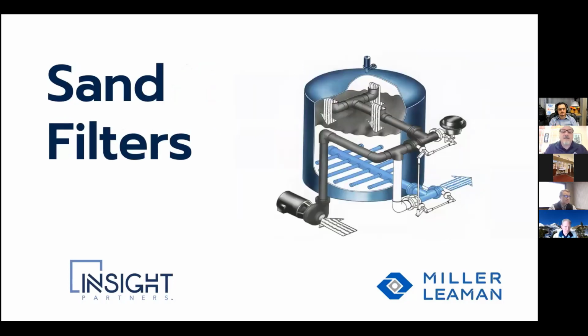Then we go on to sand filters. Sand filter technology has been around for hundreds of years. Of course, it works well. You're basically putting it into a block of sand. If you can think of it, it travels through the sand, just like it does to the aquifer in Florida and other states, and it gets some laterals, and then it gets pumped back to the cooling tower. Does a great polishing effect. It gets down to approximately 10 micron when it's brand new.